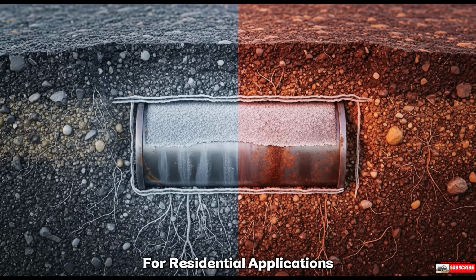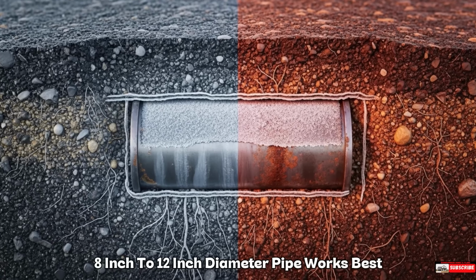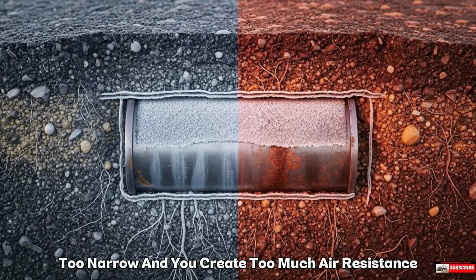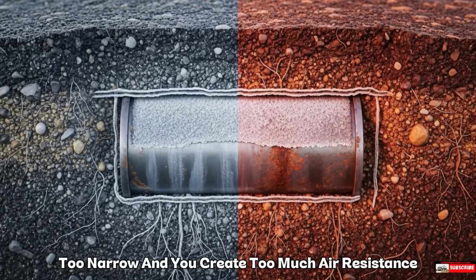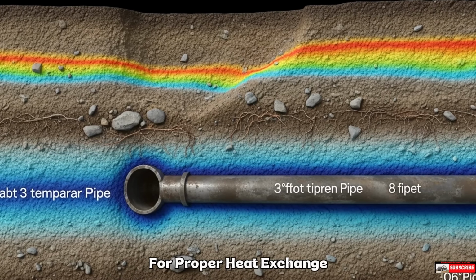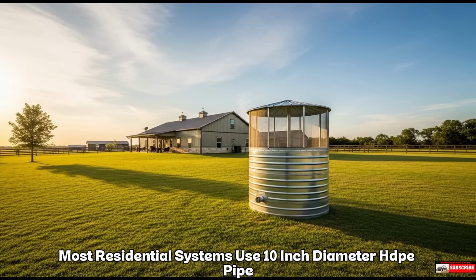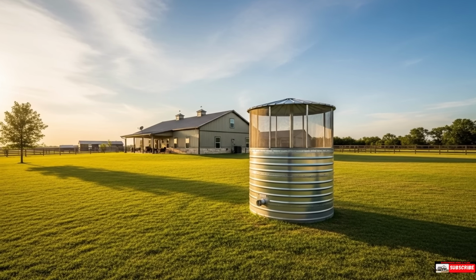Pipe diameter matters too. For residential applications, 8-inch to 12-inch diameter pipe works best. Too narrow, and you create too much air resistance. Too wide, and you don't get enough air velocity for proper heat exchange. Most residential systems use 10-inch diameter HDPE pipe.